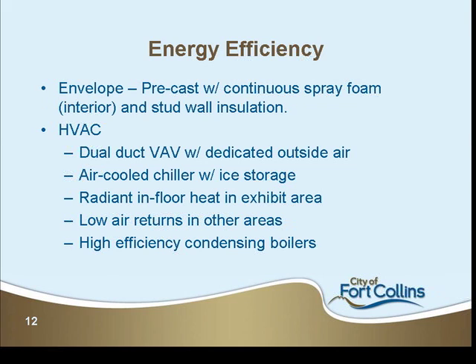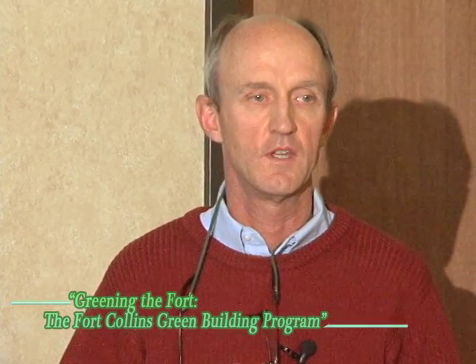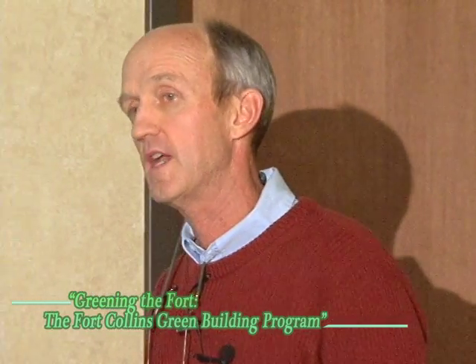For the HVAC system, they have a very innovative dual duct variable air volume system, and if you imagine a box that varies flow to a space to provide conditioning to it, and it has 2 ducts coming into it. One is conditioned air and one is outside air, and that outside air goes back to a dedicated air handler on the roof that has a heat exchanger, and so any exhaust air that's leaving the building is giving up its heat to that heat exchanger, or cool in the summertime, and exchanging that with the outside air. So when a space is unoccupied, the outside air can be completely shut down, or in shoulder season, when maybe that outside air is cool enough to condition the space, and the conditioned air duct can be completely shut down. Very innovative and efficient system.